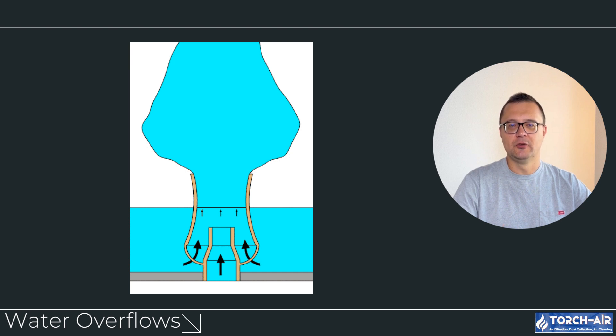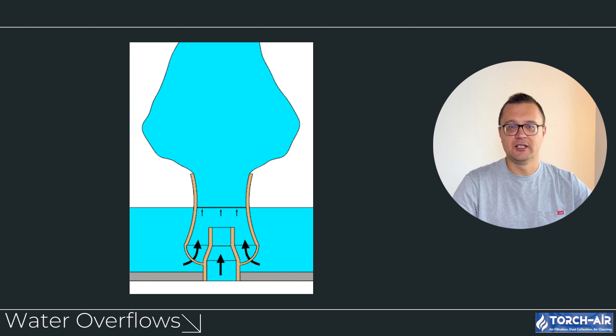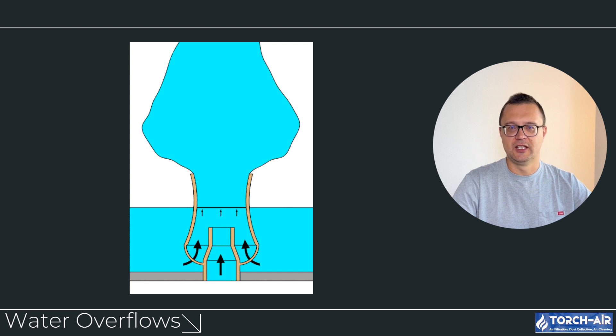While nozzles are commonly used in scrubbers, there are situations where alternative methods are more suitable. Water overflows: in some cases, scrubbers use a water overflow system instead of nozzles. This method involves directing water over surfaces where it can naturally cascade down, creating a film that interacts with the gas stream. Best for applications involving coarse dust or where you need to handle large quantities of gas with minimal energy use. Overflows are simple, low maintenance, and don't rely on high-pressure pumps or nozzles, and are especially effective for scrubbing large gas volumes without needing fine droplet atomization. Consideration: less efficient for capturing very fine particulates or gases requiring a high surface area for absorption.